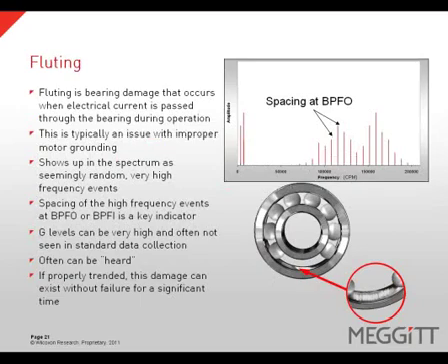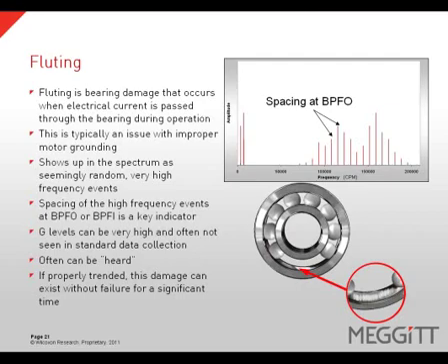Fluting is a condition that occurs when an electrical current is passed through a bearing during operation. It is typically caused by improper motor grounding and will show up in the vibration spectrum as seemingly random, very high-frequency events. The spacing of these high-frequency events is a key indicator, and they will be spaced at ball-pass frequency outer race, ball-pass frequency inner race, or both. The acceleration G levels can be very high and can be easily missed with routine data collection. Fluting can often be heard, and if properly trended, this damage can exist without failure for a significant amount of time.